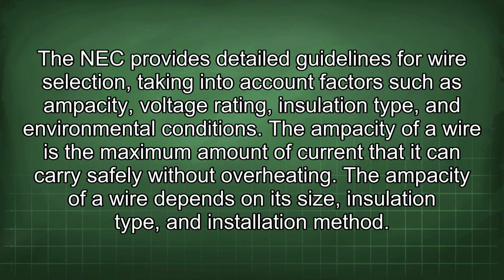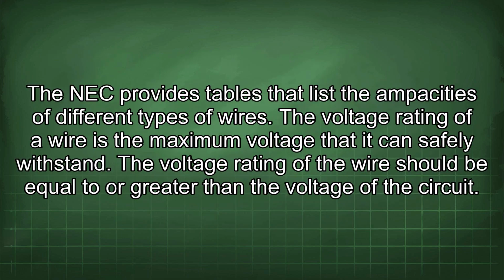The NEC provides detailed guidelines for wire selection, taking into account factors such as ampacity, voltage rating, insulation type, and environmental conditions. The ampacity of a wire is the maximum amount of current that it can carry safely without overheating. The ampacity of a wire depends on its size, insulation type, and installation method. The NEC provides tables that list the ampacities of different types of wires.